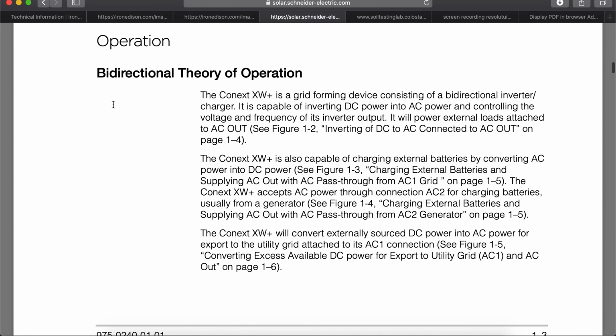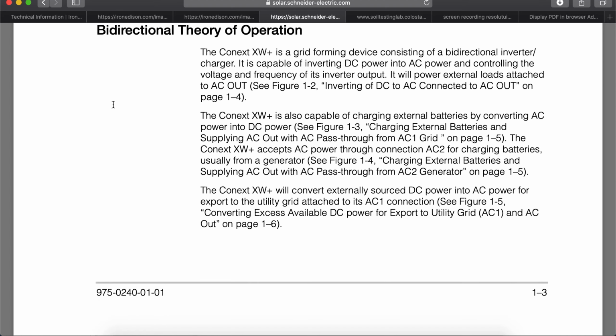Operation. Bidirectional theory of operation. The Conext XW Plus is a grid-forming device consisting of a bidirectional inverter charger. It is capable of inverting DC power into AC power and controlling the voltage and frequency of its inverter output. It will power external loads attached to AC output. See Figure 1-2, inverting of DC to AC connected to AC output, on page 1-4. The Conext XW Plus is also capable of charging external batteries by converting AC power into DC power. Figure 1-3, charging external batteries and supplying AC output with AC pass-through coming from AC1 input grid, on page 1-5.